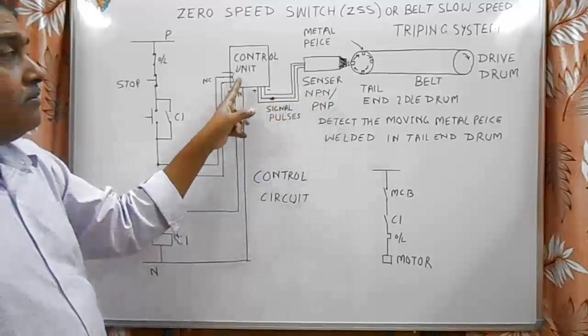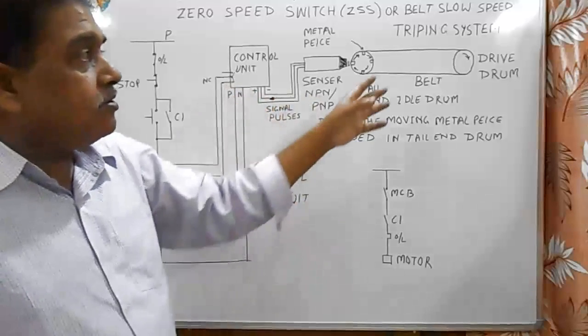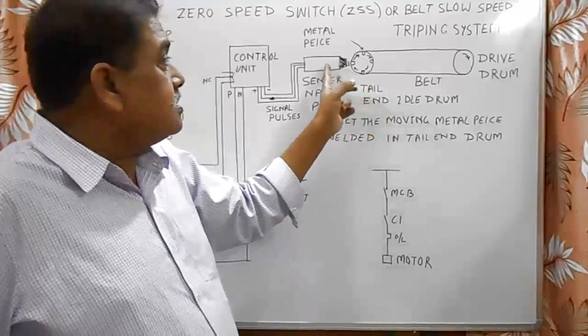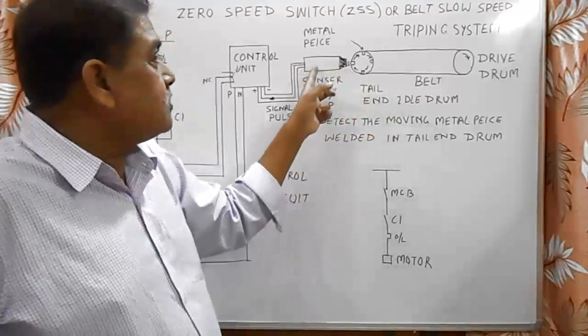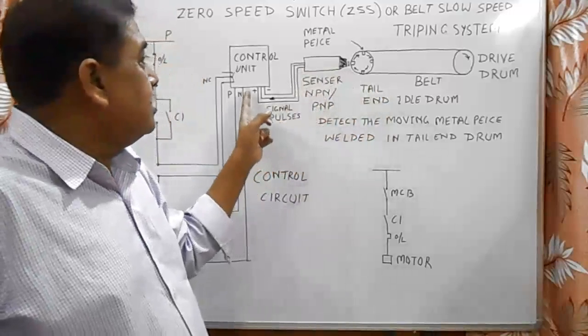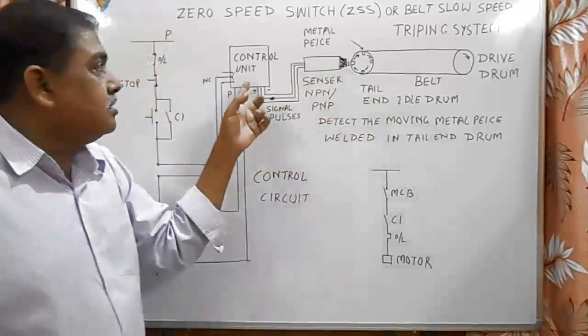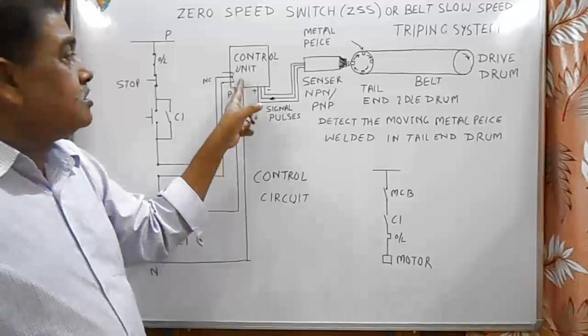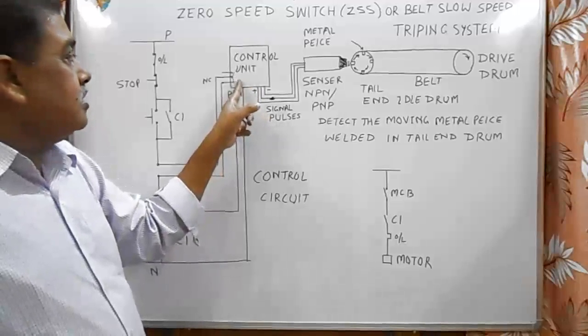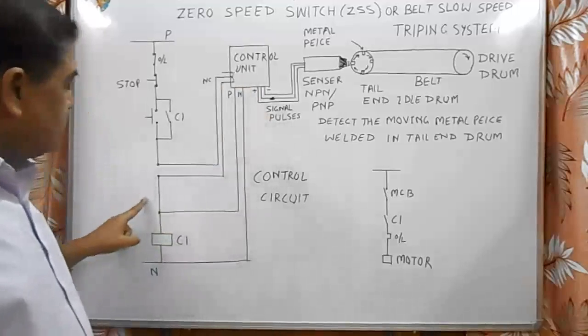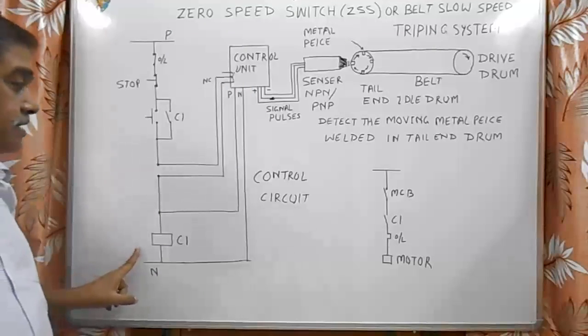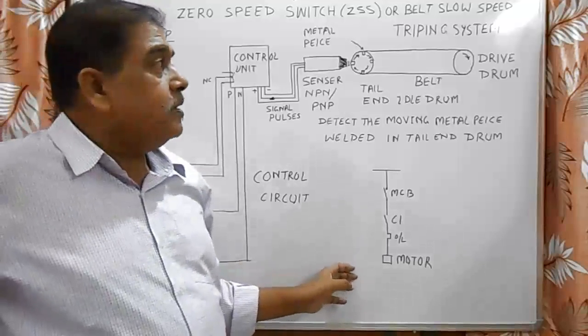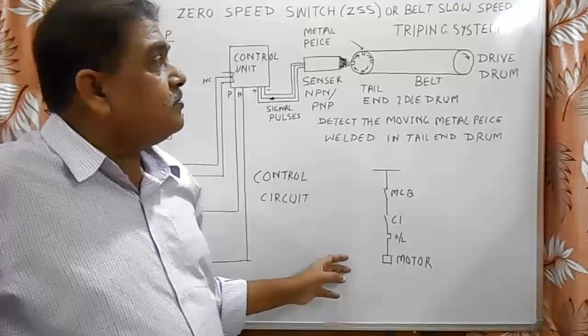Whenever due to some overload conditions this belt speed slows down, then the pulse frequency goes down and this control unit senses that the pulses are not coming at a proper speed. So this makes this contact break, and this breaks the supply of the C1 contactor. The contactor drops down, so the motor stops at slow speeds.